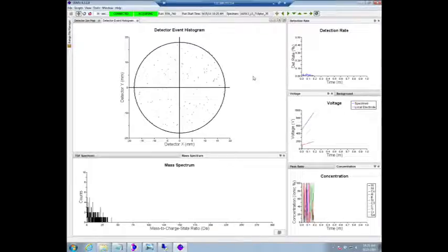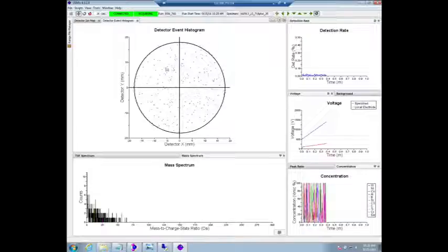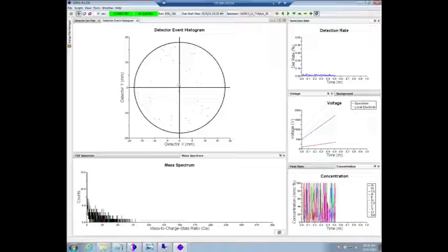Two thumbs up. Two thumbs up. So here you can see the voltage ramping up, and here you can see the detection rate. So right now we're just getting some stray atoms that are on the surface coming off, but at least the field is high enough to get some signal. If the specimen is very blunt, you probably will only get some stray hits here.